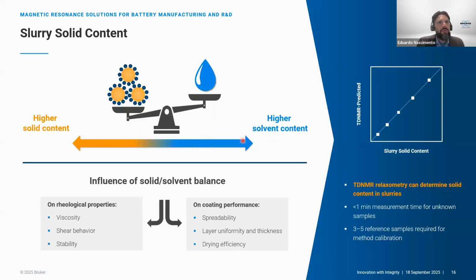So the last application I will talk about here, as I said, is that you can correlate the TD-NMR information with other parameters. For example, we normally correlate that with rheological properties like viscosity, shear behavior, and stability. And we have been using that to calculate the solid fraction content of slurries as well. So provided that you can calibrate the system, and you need just 3 to 5 reference samples, you calibrate the system once, and then you don't need to do that anymore. Of course, unless you are changing recipes or working with different types of slurries and so on. But once you have a calibration curve, you can get your results quite fast.